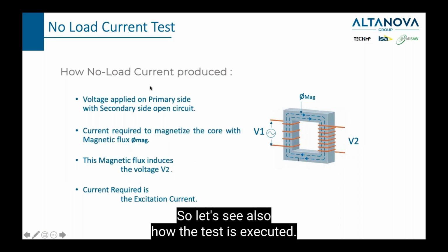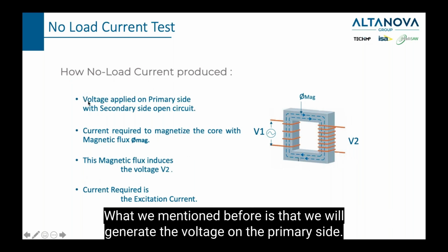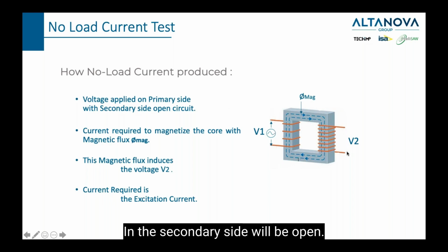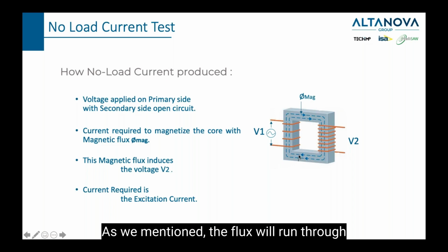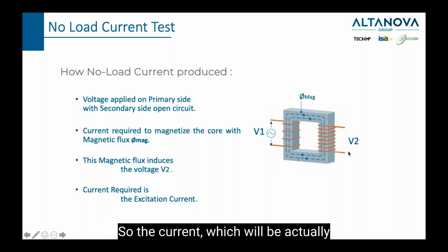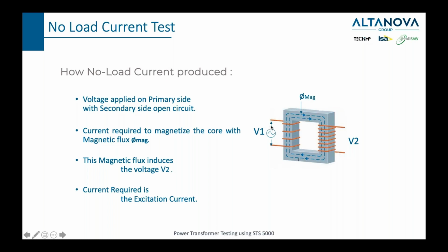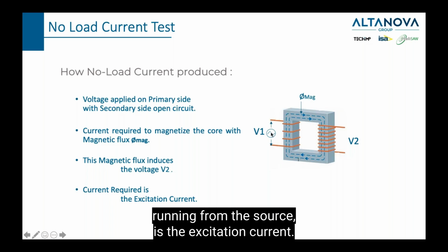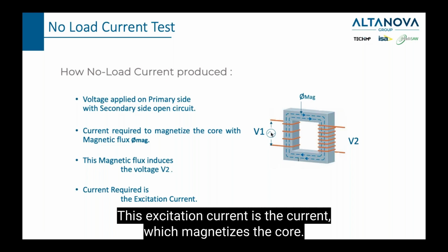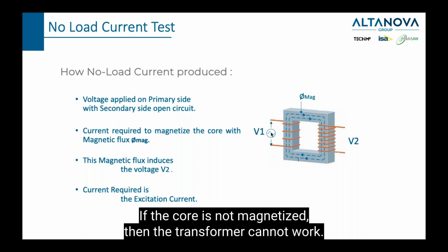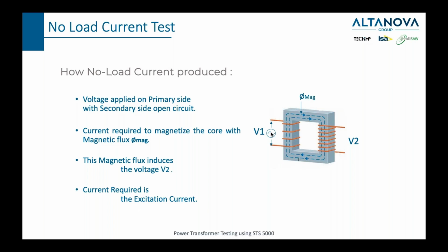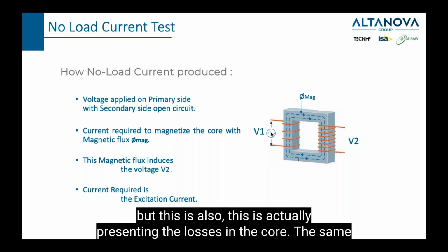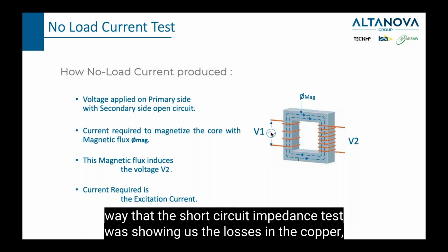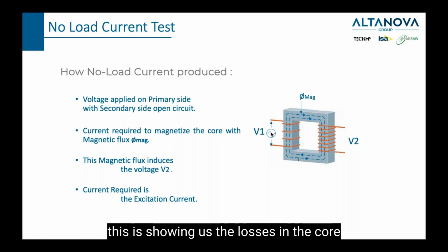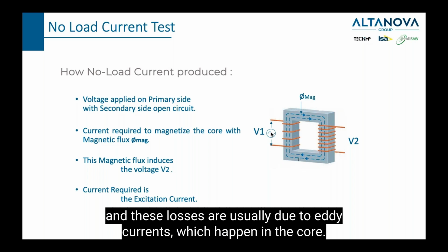So let's see also how the test is executed. What we mentioned before is that we will generate a voltage on the primary side and the secondary side will be open. As we mentioned, the flux will run through the core and it will induce voltage V2. So the current which will actually be running from the source is the excitation current. This excitation current is the current which magnetizes the core. If the core is not magnetized, then the transformer cannot work. So this is also a loss, but this is actually presenting the losses in the core. The same way that the short circuit impedance test was showing us the losses in the copper, this is showing us the losses in the core, and these losses are usually due to eddy currents which happen in the core.